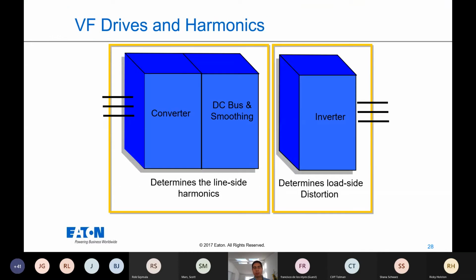Moving forward, let's talk about some filtration here. The AZ Water Committee wanted me to focus on what filters, what types do we have, and input and output filtration when applying a VFD on the system. So there are two types of filters that we talk about here. Input filters are for the line harmonics. Output filters are for the lengths from your VFD to the motor, and they're both very important considerations when designing and installing your motor pump VFD application.